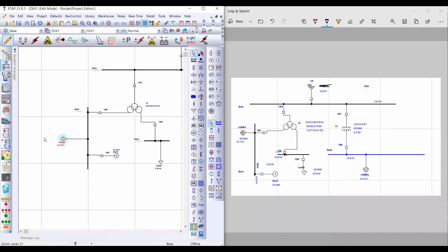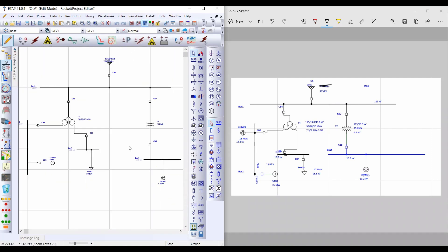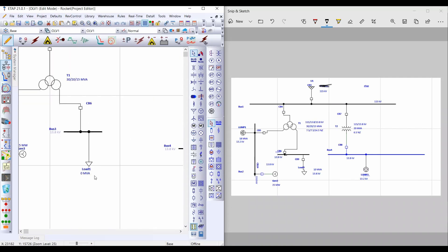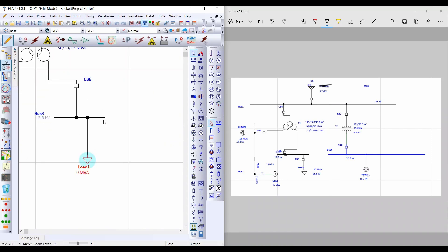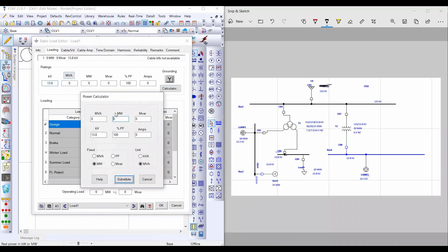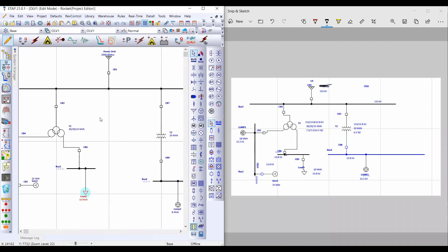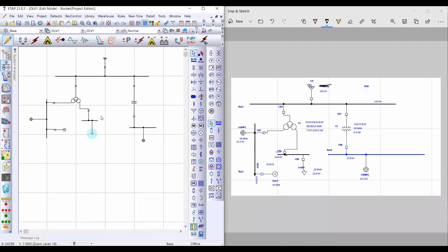Now I have finished inserting all technical data for all AC elements in this single line diagram, except for one remaining load. The value of this static load is 10 MVA. From Loading, then Calculator, insert 10 MVA. Select Fixed MVA, and since it is a static load the power factor will be 100. Click Substitute. Now I have finished inserting all technical data for all AC elements in this single line diagram.